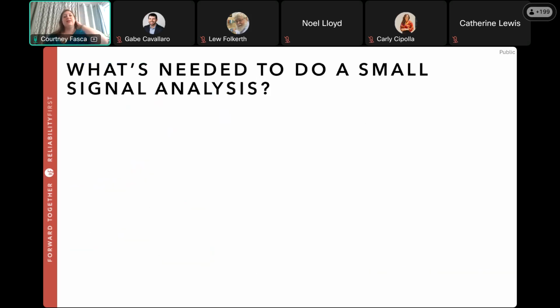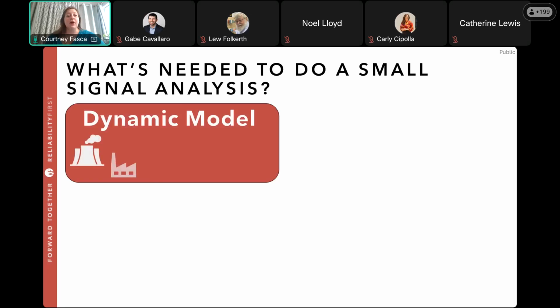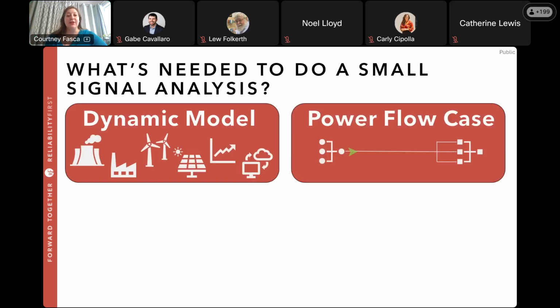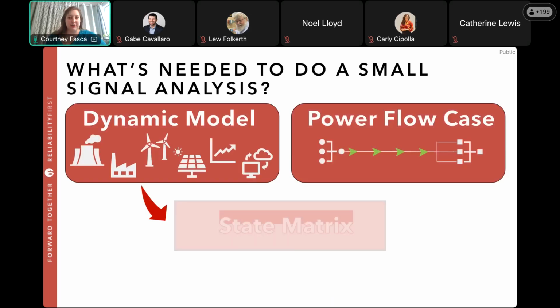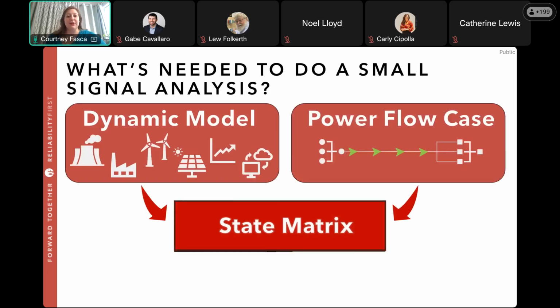Small signal stability analysis requires the same data that would be needed for transient stability or dynamic analysis. Basically, we need models for all the dynamic components in the system, like conventional machines, FACTS devices, dynamic loads, IBRs. Any small signal stability analysis tool uses these dynamic models and the power flow case to create something known as a state matrix. The elements of the state matrix are direct functions of the parameters of the dynamic devices, such as the damping and inertia parameters of conventional machines.